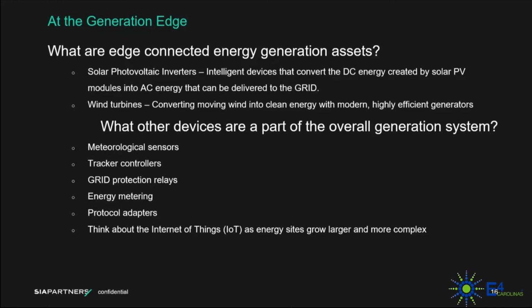We also look and talk to grid protection relays. So an SEL, say 751 relay, which monitors current and voltage. And when things get out of parameter, they will trip, opening a main breaker, signaling an alarm, setting off a problem for somebody to say, we need to do something about this. We're seeing this more and more on grid devices everywhere on the grid.